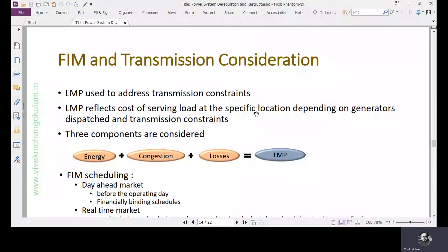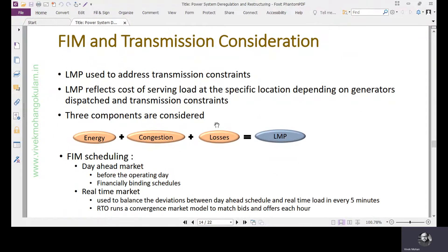Now we move on to fully integrated markets with transmission consideration. With transmission consideration, we use location marginal price to settle the market. The location marginal price is derived from three different components: energy, congestion, and losses. The location marginal price is location specific and zone to zone it differs.